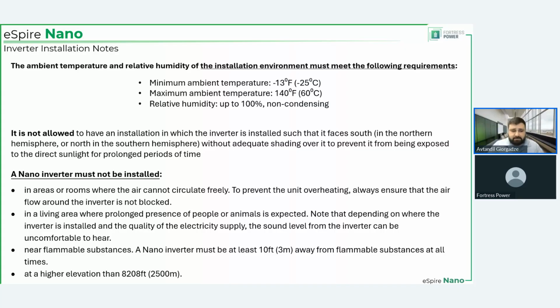Again, this comes down to the fact that this is an air-cooled unit, and the higher the elevation, the less the density of the air around the unit, and the lower the density, the lower the cooling effect. Technically, you can mitigate that with higher speed, but these fans on the inverter can only spin so fast.